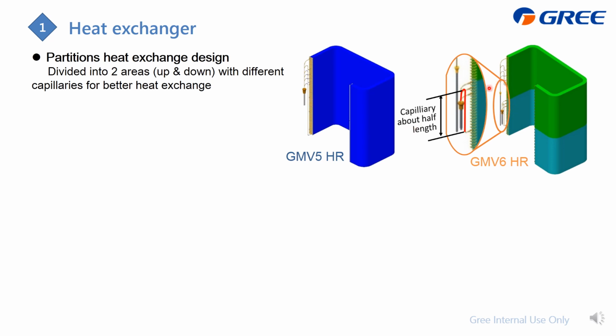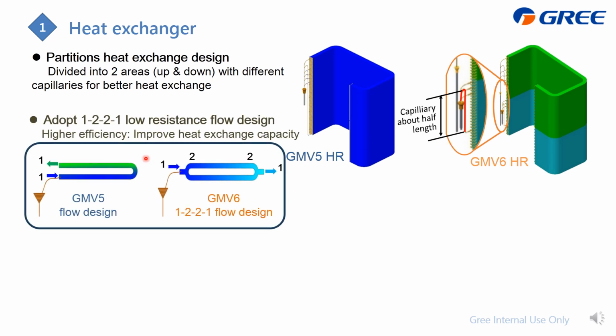And for GMV6, we also adopt the distributor to distribute the liquid refrigerant. But as we divide it into two, the length from the distributor to the furthest pass is only half, so it makes control in mass production easier. And the next is from the distributor to the outdoor heat exchanger. For GMV5, the flow is only 1. For GMV6, from here it is 1 and then divides into 2, and then here we combine these two together and make it 1. With this design, we can raise the heat transfer efficiency, as shown either by simulation or by test results.